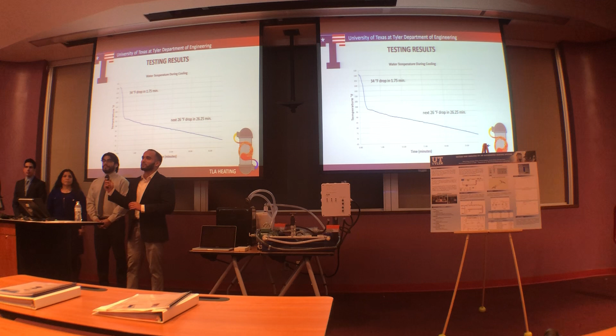So this next chart pretty much shows our testing results when we went into automated mode. So we can see the increase in temperature, and this is again in about 2.5 minutes. But we actually tested it from room temperature all the way to our max temperature of 140 degrees Fahrenheit. So what happens is that when we reach that temperature, our system will either kick into recirculation mode or send its output to the heat exchanger. Now, we did have a slight overshoot of about 1.4 degrees Fahrenheit, but the recovery time of this was about 35 seconds. And then after that, once we're either sending to the heat exchanger or recirculating, we have a temperature drop of less than a degree per minute.